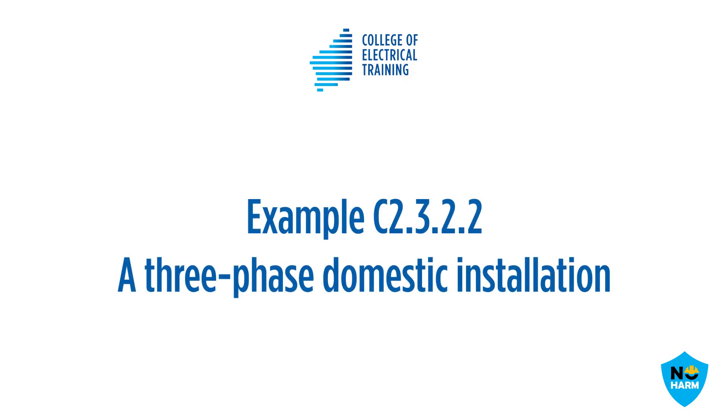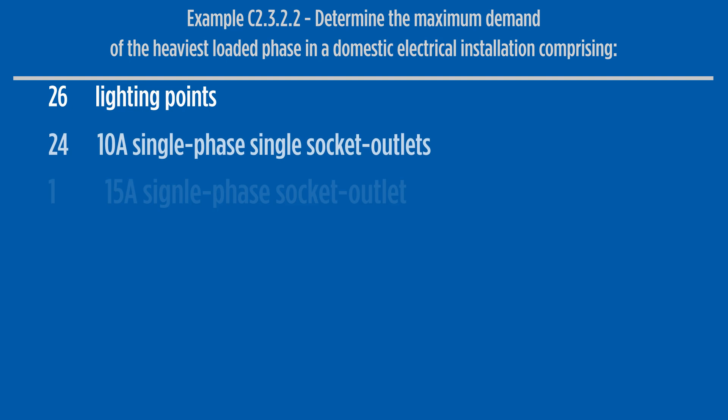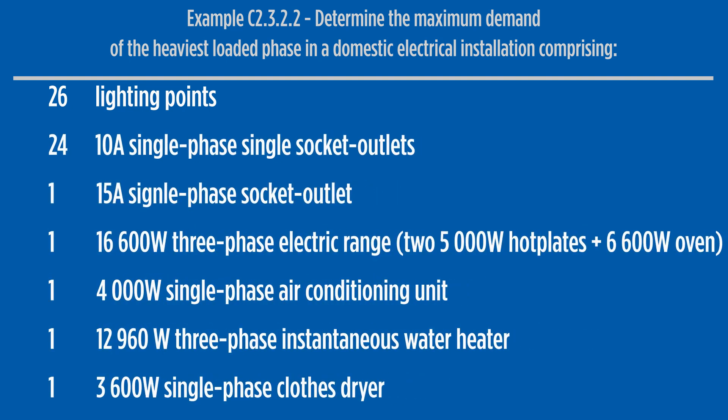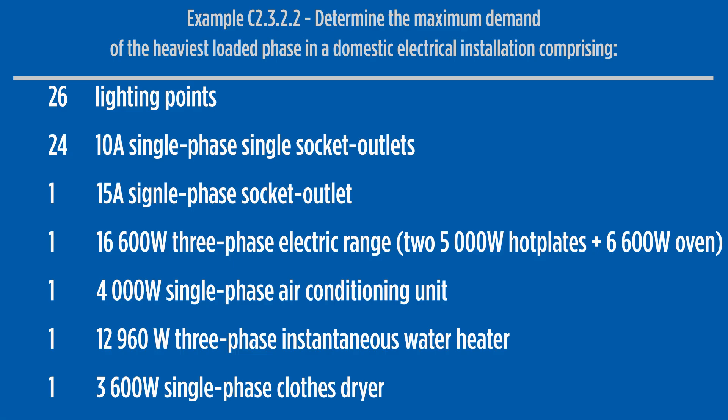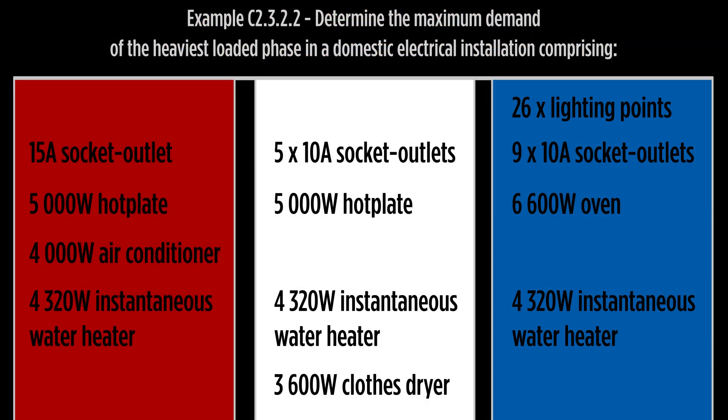Example C2322 gives an example of a single domestic dwelling with a three-phase supply and uses tables C1, columns 1 and 2, for calculation purposes. The process is the same as the previous example. However, loading is spread over three phases, and phase loading needs to be kept as close as practicable when calculating maximum demand.